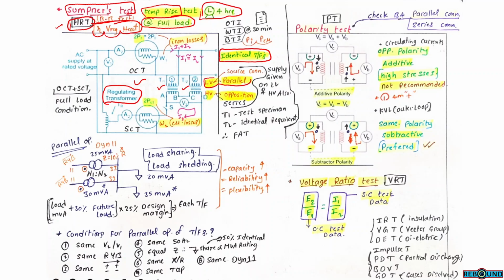LV sides are connected in parallel across the source and HV sides are connected in series opposition. So this is transformer 1, this is transformer 2. The primaries are connected in parallel where the secondaries are connected in series opposition. This is the primary side voltmeter, ammeter, wattmeter. This is the secondary side voltmeter, ammeter and wattmeter. On the primary side, this wattmeter will read the total iron losses of both the transformers. On the secondary side, this wattmeter will read the total copper losses of both the transformers.